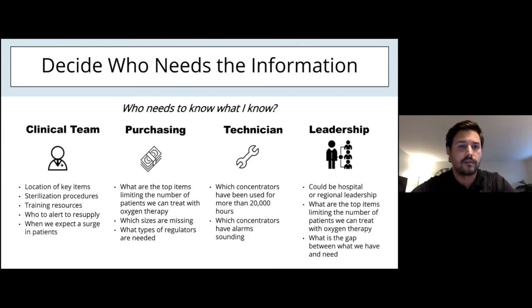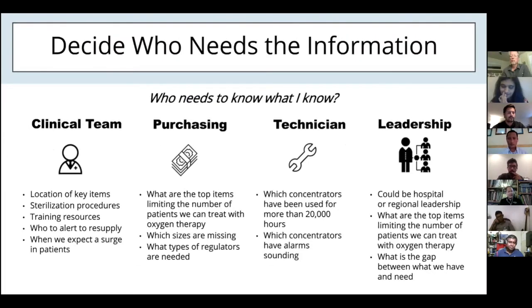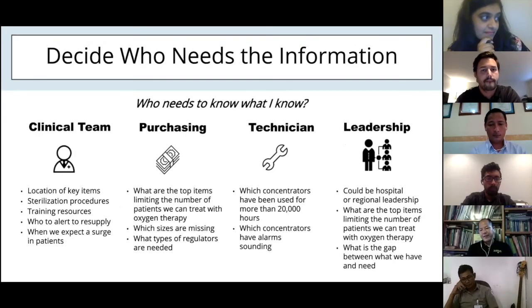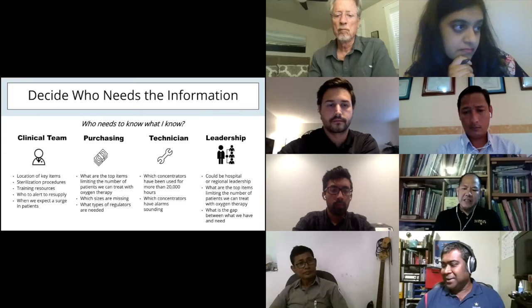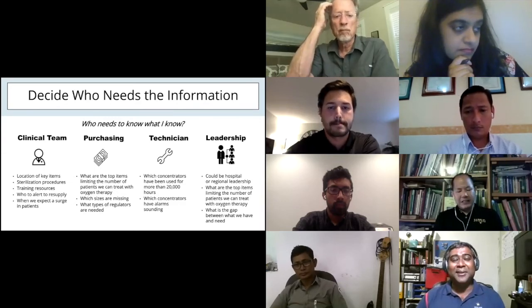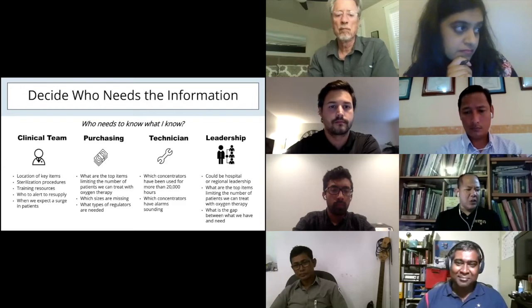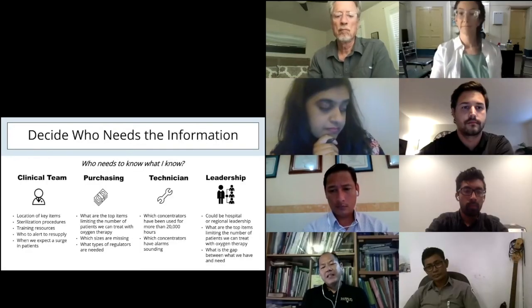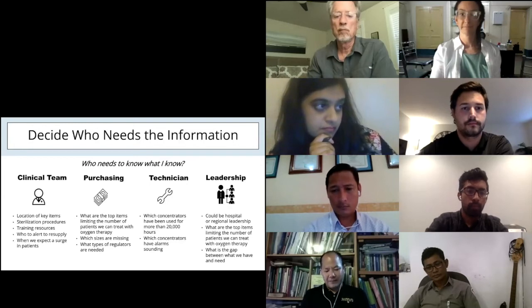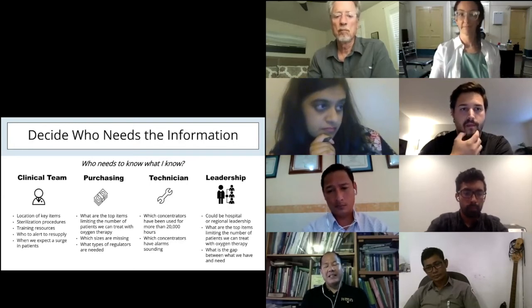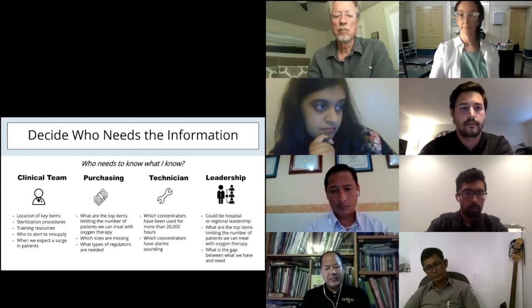Guna, real quick, can you tell your story about the alarms that you found and the situation with those? Yeah, some of the technicians find the alarm really annoying. So what happened is they intend to not diagnose the device, but they intend to cut the alarm. So you still got the same problem running in the machine, but the alarm is missing now. So they cut the buzzer inside the system, and they don't really repair the machine actually. So this is what happens.